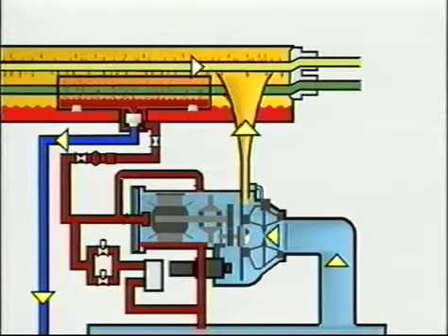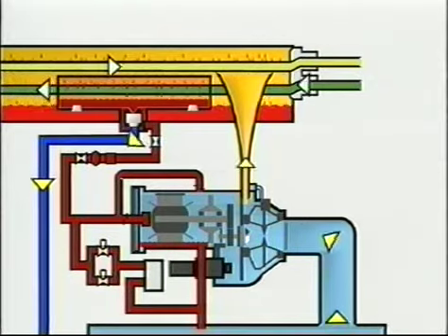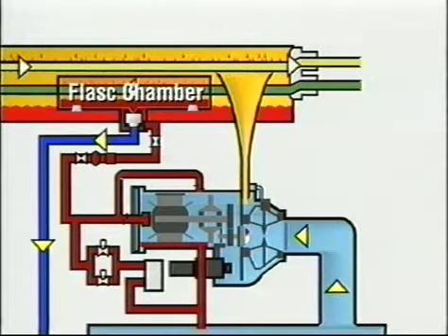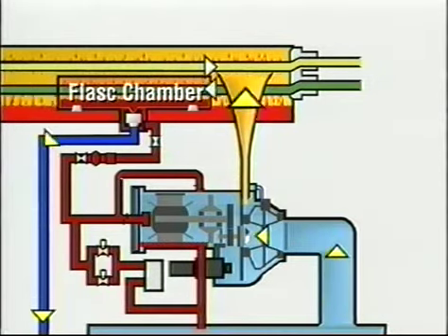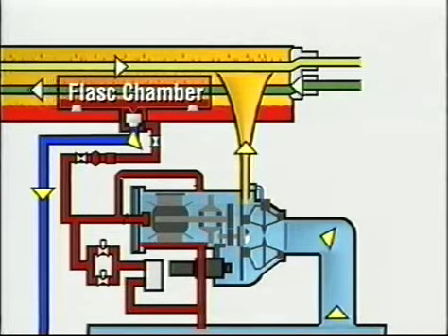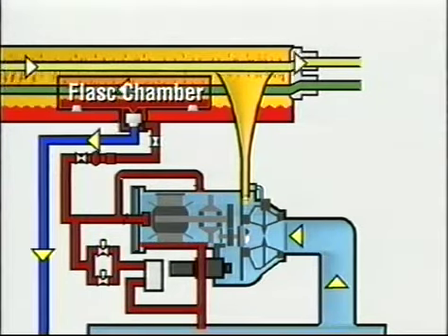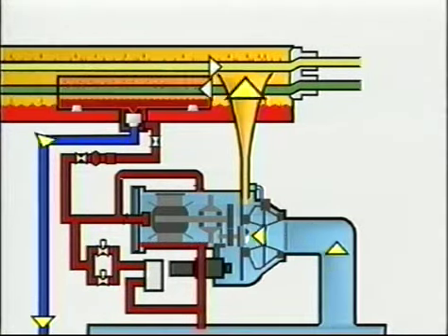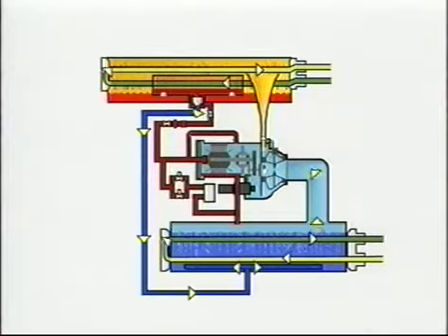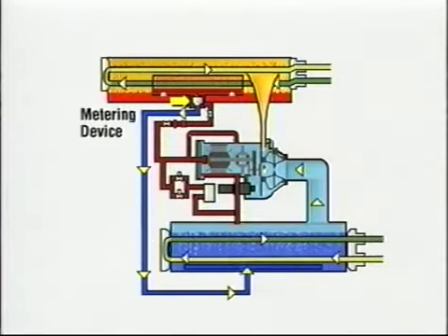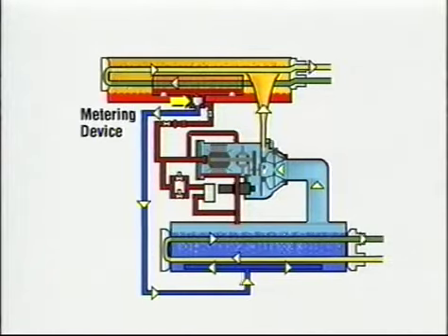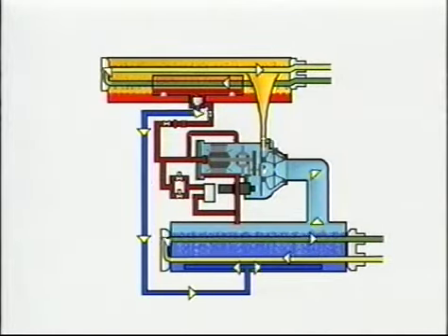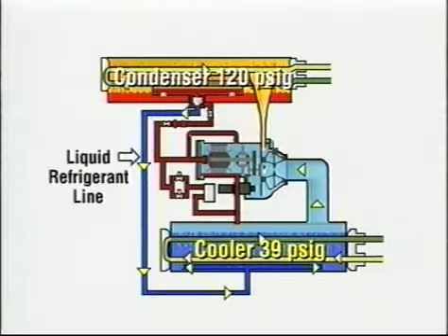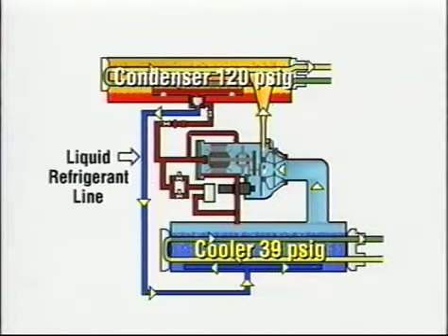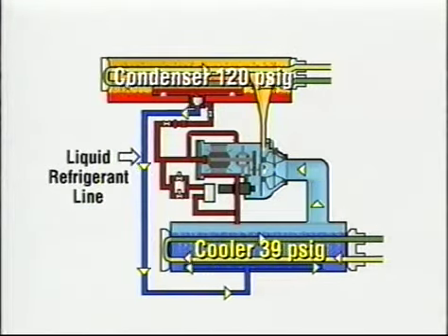The condensed refrigerant liquid drains to the bottom of the shell, where it passes through orifices into the flash chamber. Since the chamber is at a lower pressure, part of the liquid refrigerant flashes to vapor, thereby cooling the remaining liquid. The cycle is completed as the cooled liquid refrigerant flows through a metering device and returns to the evaporator. As shown, the float valve controls the flow of liquid refrigerant between the condenser pressure of 120 psig and the evaporator pressure of 39.0 psig.